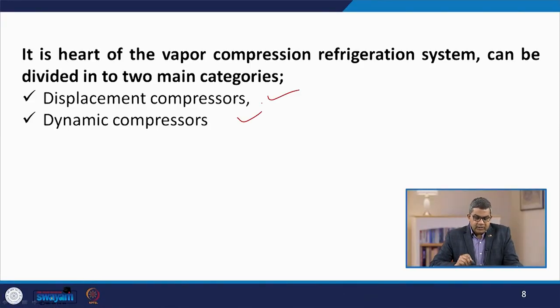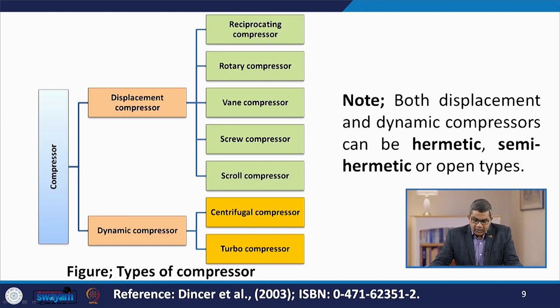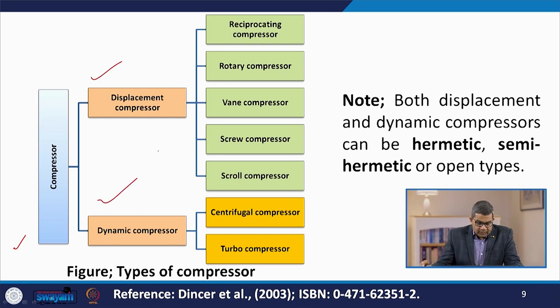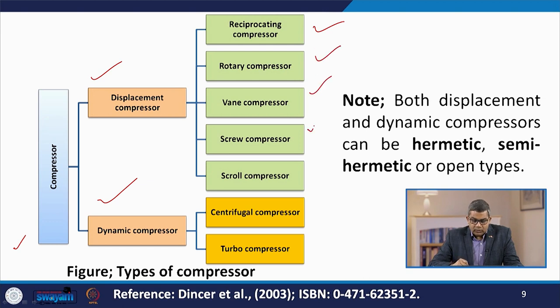As the heart of the vapor compression refrigeration system, the compressor can be divided into two main categories: displacement compressors and dynamic compressors. Displacement compressors are subdivided into five categories: reciprocating, rotary, vane, screw, and scroll compressors. Dynamic compressors are subdivided into centrifugal and turbo compressors. Compressors may also be hermetic, semi-hermetic, or open type.